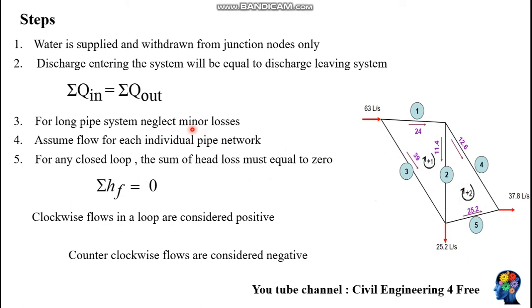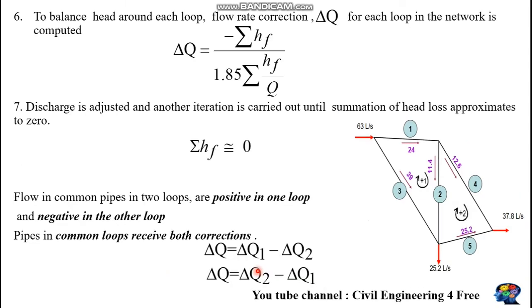For any closed loop, the sum of head loss due to friction must also be zero. Regarding flow direction, clockwise flows are assumed to be positive and counterclockwise flows are considered negative. Using the Hardy Cross method, you first have to determine the discharge correction. The discharge correction is given by the ratio of the summation of head loss due to friction to 1.85 times the summation of the ratio of head loss due to friction to discharge.